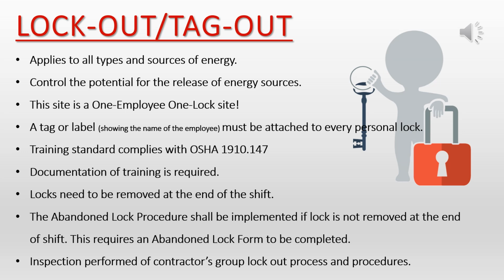Locks need to be removed at the end of shift. The abandoned lock procedure shall be implemented if a lock is not removed at the end of shift. This requires an abandoned lock form to be completed. Inspection performed of contractors' group lockout process and procedures.